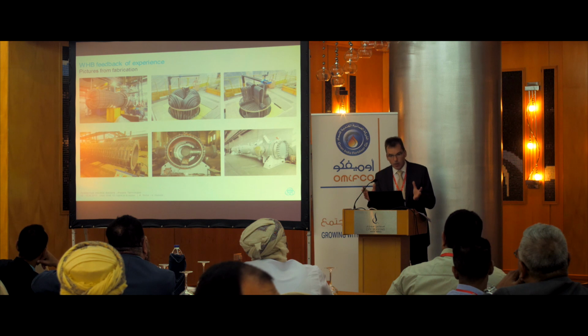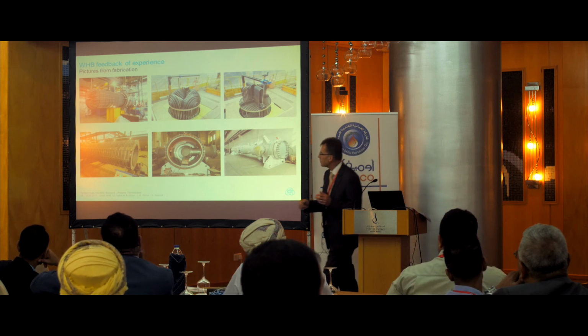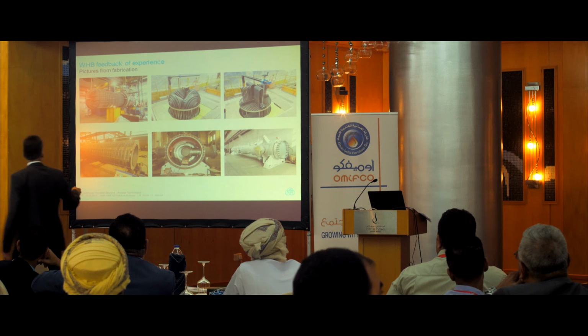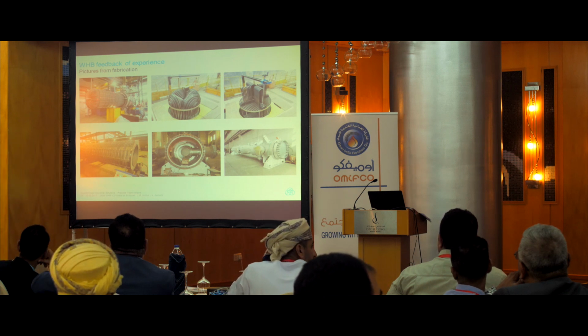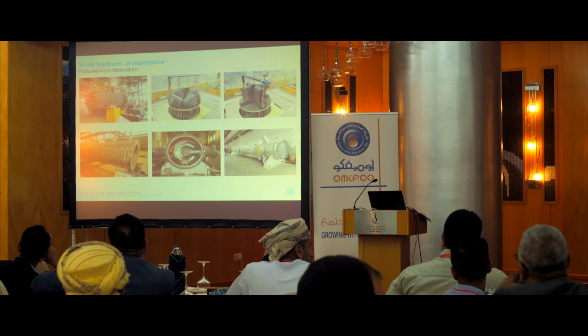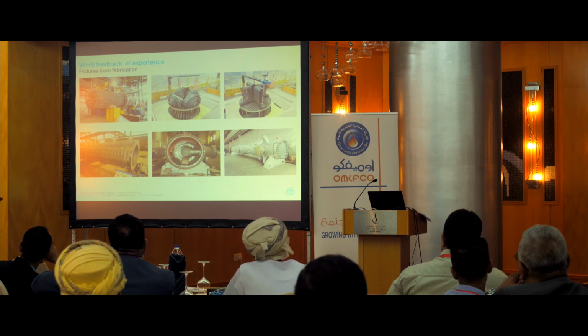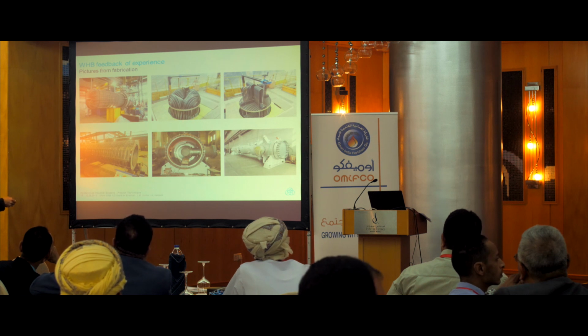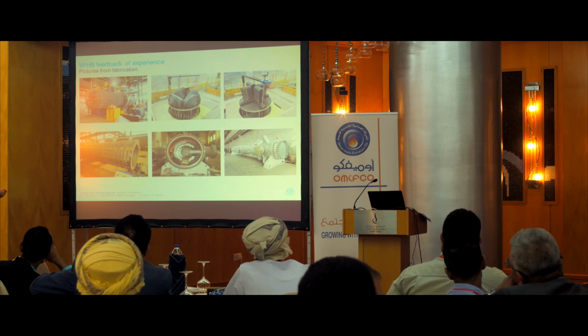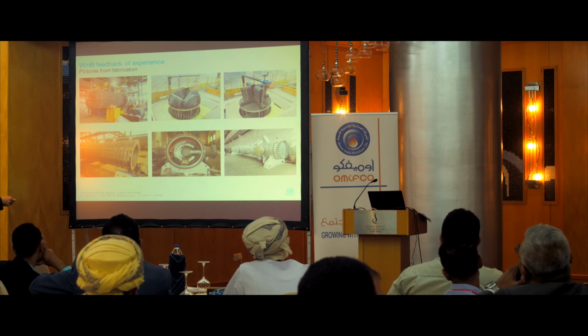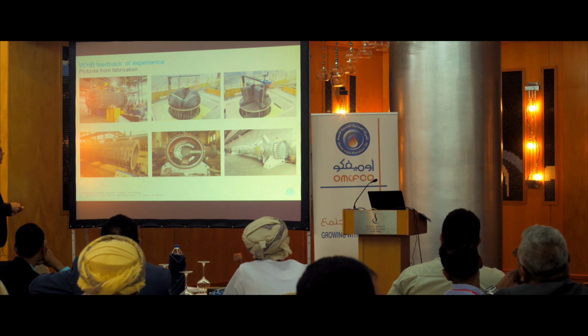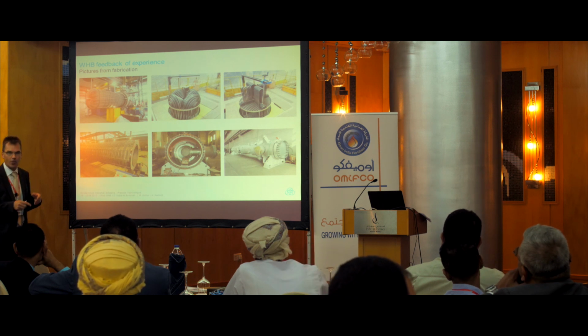One more slide regarding how it looks like, so that you get an impression of size. Again, on the left side, you see the so-called fountain type heat exchanger. Here are the hot part, then goes down cool tubes. Here we have a hot-cold design. That means hot gas like this, cold gas goes down here in 4 sections. This is waste heat boiler number 2. This is waste heat boiler number 1. Here you see a typical picture that it is very important that tubes will be inserted in a certain order, because if you don't do it, you have no access anymore later on to the welds.